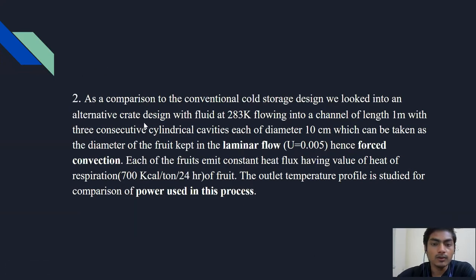That was our part one of the problem statement. The part two is, as a comparison to the conventional cold storage design, we looked into an alternative crate design with fluid, which is water, at 286 Kelvin flowing into a channel of length one meter with three consecutive cylindrical cavities, each of diameter 10 cm, which can be taken as a diameter of fruit kept in the laminar flow, which has a velocity of 0.005 m/s. Hence, forced convection is happening here. Each of the fruits emit constant heat flux having value of heat of respiration, that is 700 Kcal/ton/24 hr per fruit.